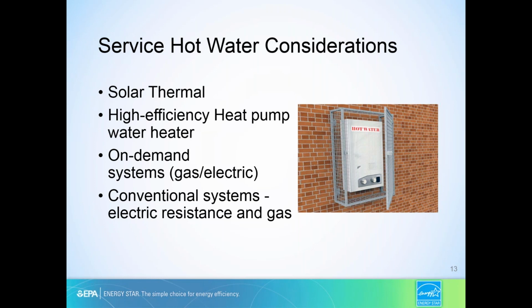Another thing to look at is service hot water considerations. In several of our buildings across the city, we've opened up mechanical room doors and seen 90 kilowatt electric resistance heaters for a community center. We don't need 200 gallons of standby hot water when there's not a commercial kitchen in the space.